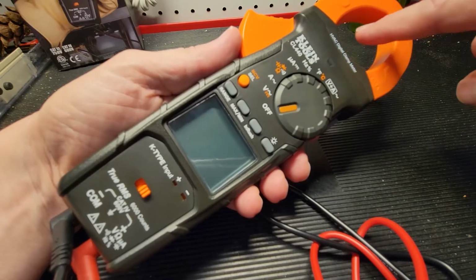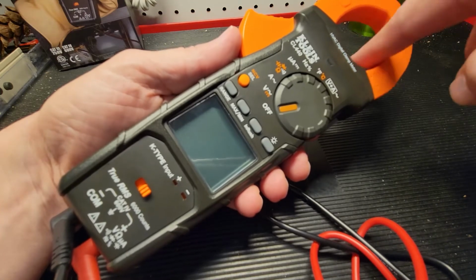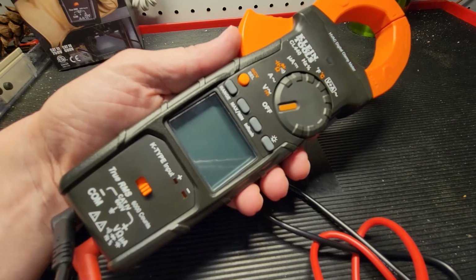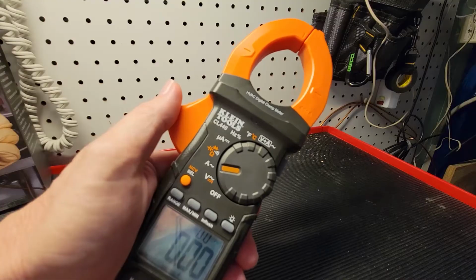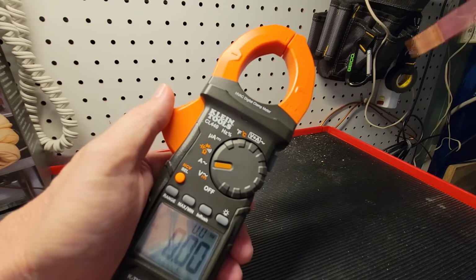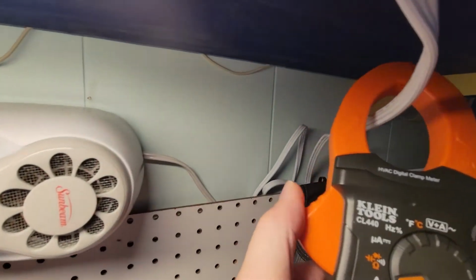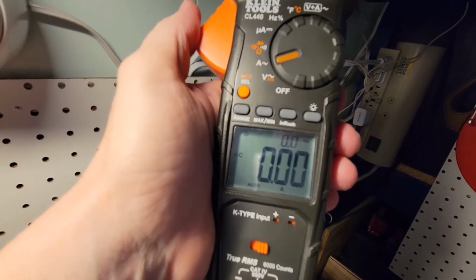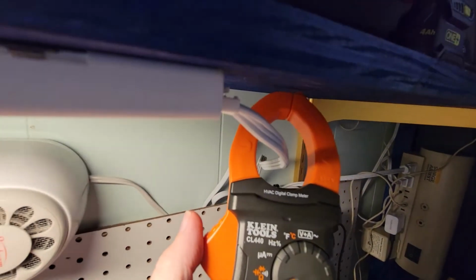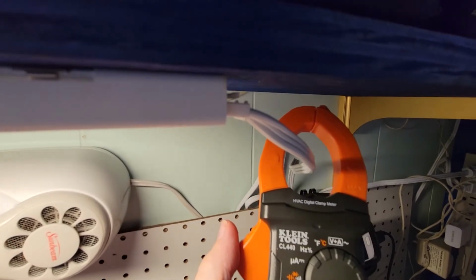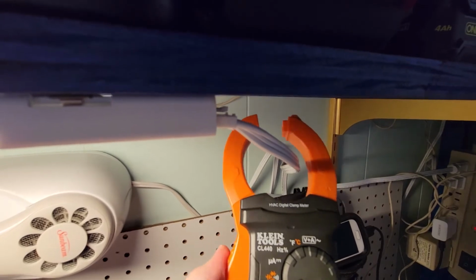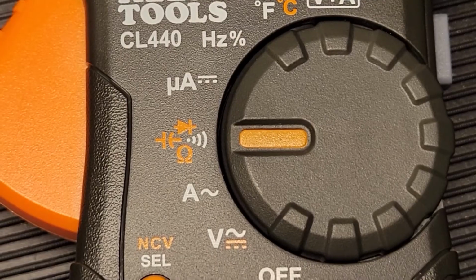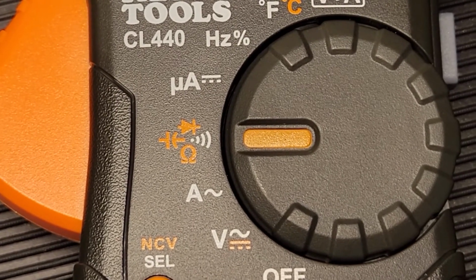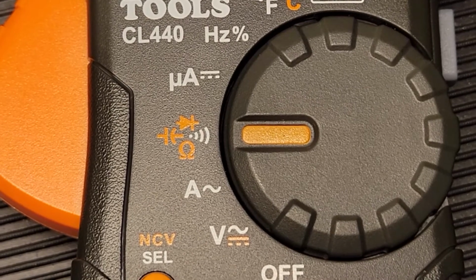A few quick tips. One, when measuring current, make sure the wire is perpendicular to the loop and that it's in the crosshairs. Two, make sure to remove your leads before using the clamp to make measurements. When attempting to measure a current with the clamp, recall that it's a single wire. If you try to do something like a cable, your reading is going to be wrong because the cable will zero out to 0 amps because you have current going through and you also have ground or neutral in there. So that will zero out your results, and you need to break out the individual leads in here to get an accurate reading. And finally, when measuring ohms or continuity, make sure there is no power on the circuit, otherwise you will ruin this device.